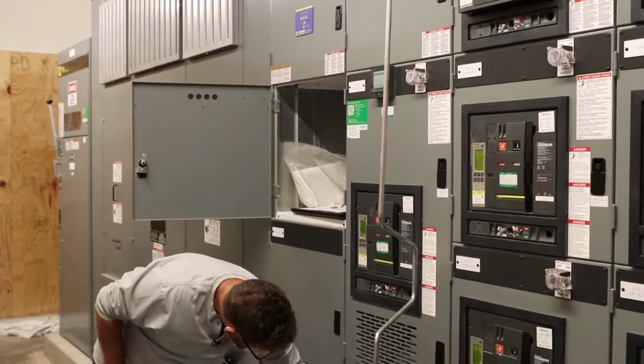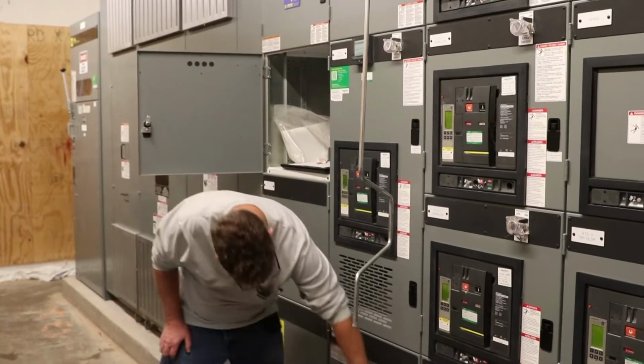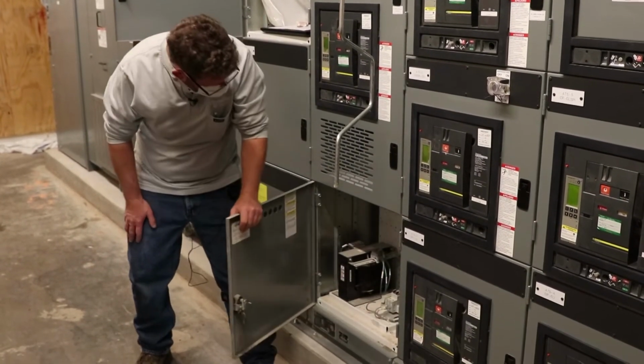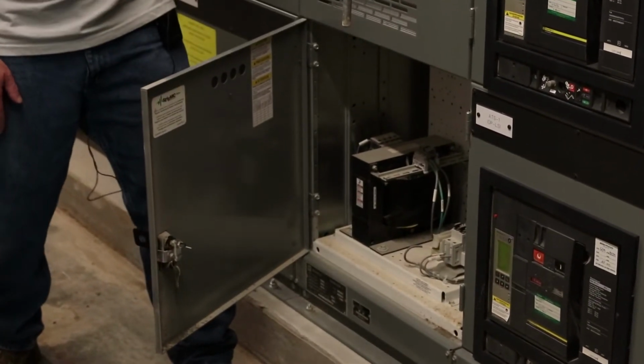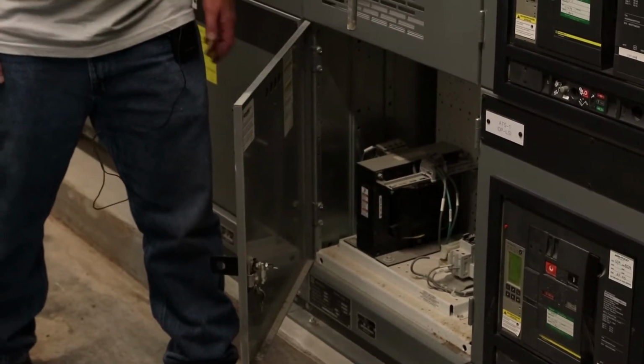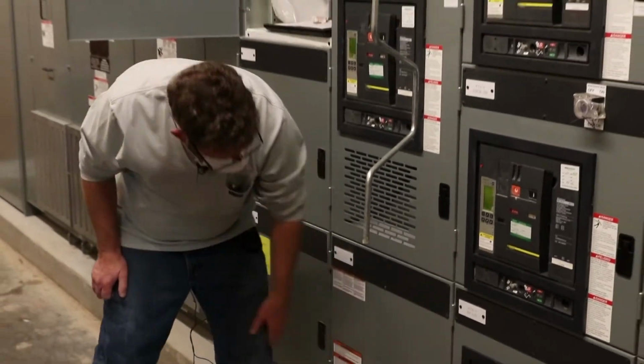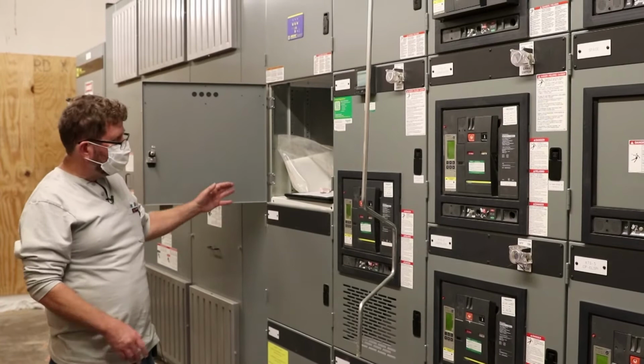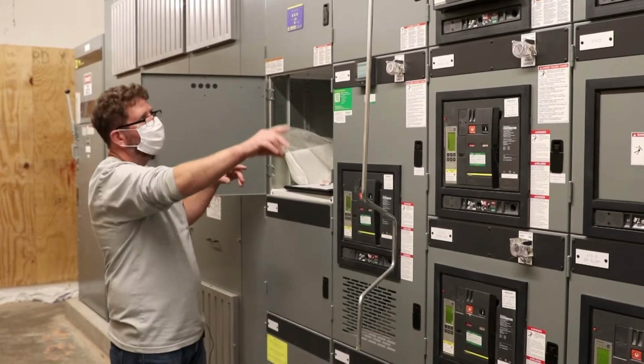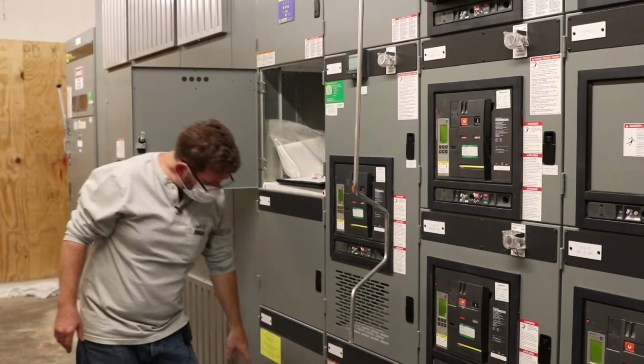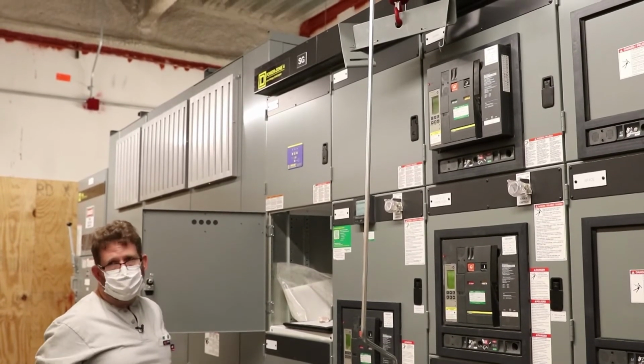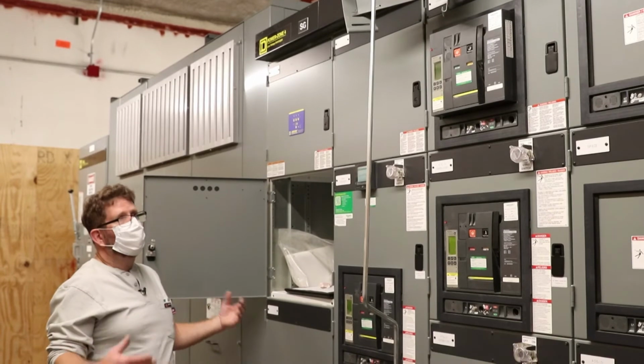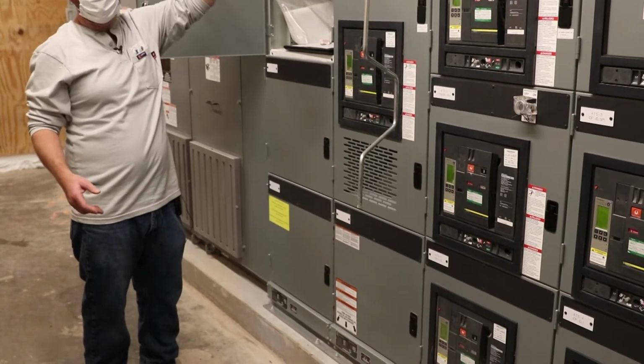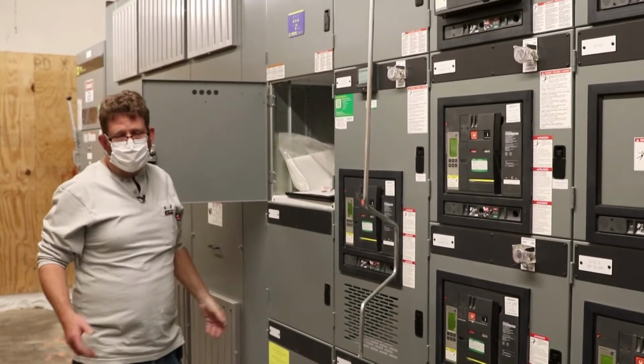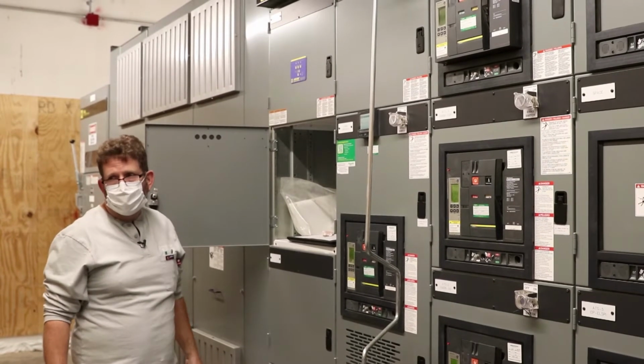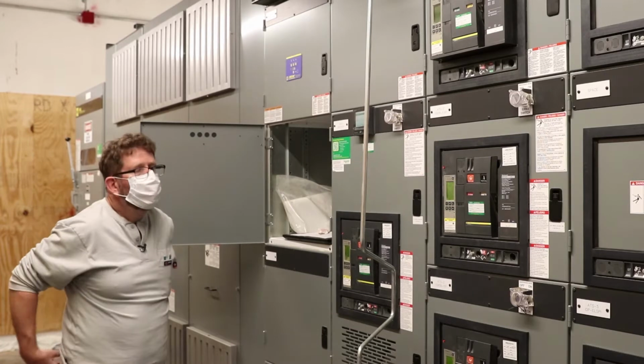A fuse disconnect switch is for the meter, and it's going to also, actually that may not be, so the control power transformer is probably here. We also have a control power transformer that supplies all the control power for the lights on the breaker and any other control functions you have in the gear. Any interconnections between this section and other sections go through a wiring trough in the top and a wiring trough in the bottom. During maintenance, it should be opened up, cleaned, and checked. What I've seen over the years is mice will get into these wire compartments and they seem to just enjoy chewing on the wires. Insulation, right? Yeah, it's delicious, apparently.